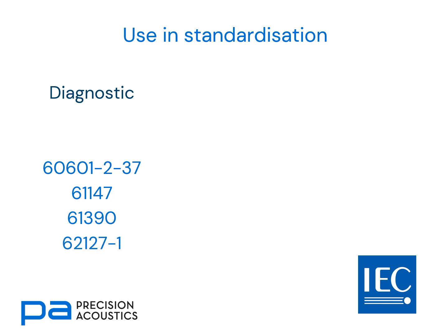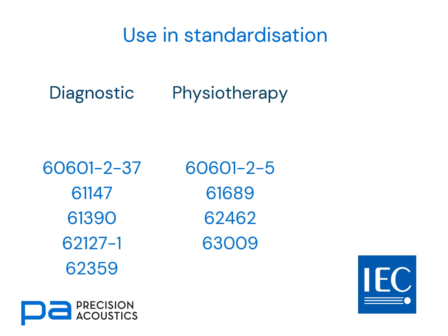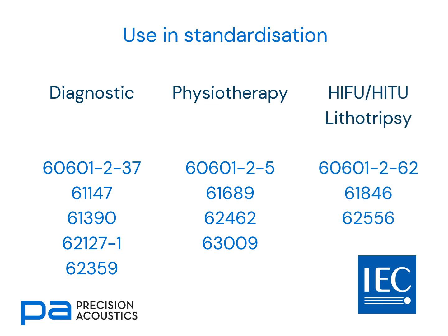Ultrasonic intensity is widely used throughout the standardisation process. If we consider just the IEC family of documents, we note that there are multiple documents in the diagnostic, physiotherapeutic, and HIFU, HITU and lithotripsy considerations, all of which use ultrasonic intensity as a means of field classification and characterisation.